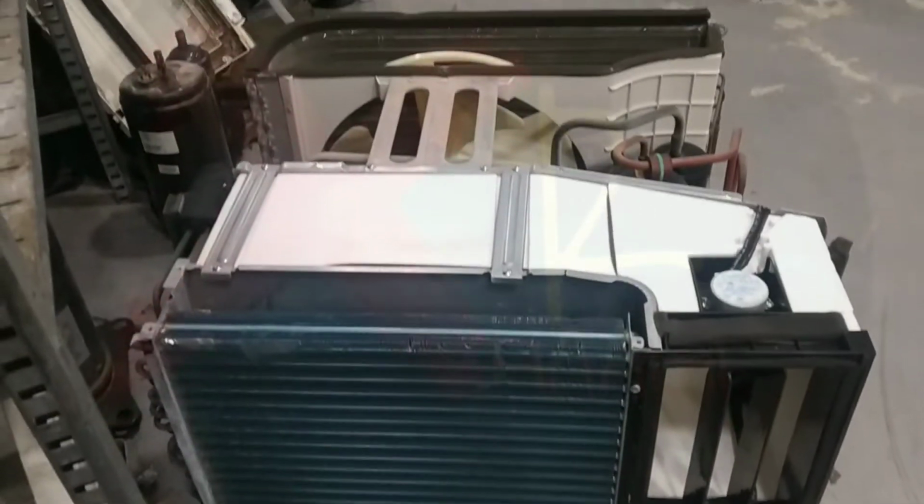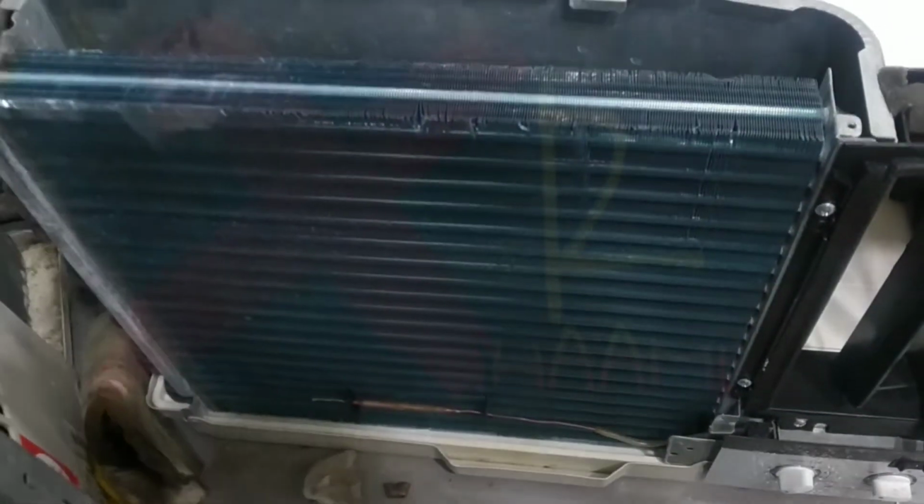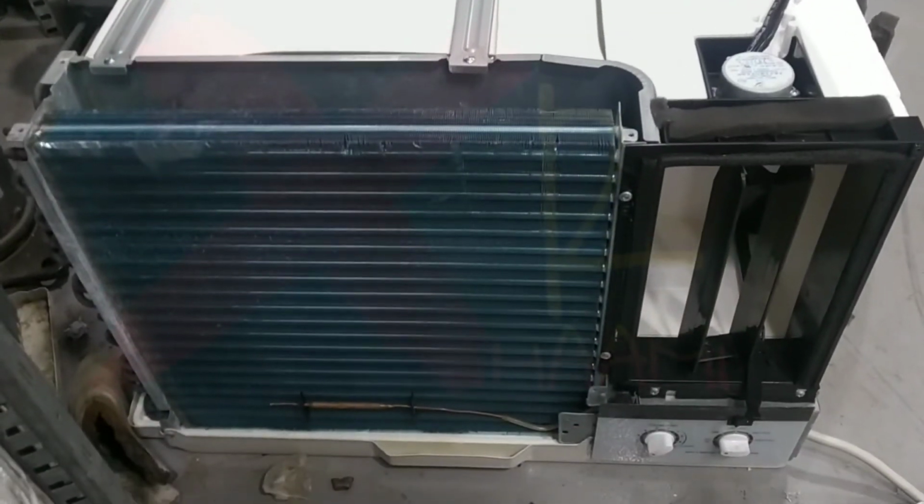This is also a reason for icing over: if your air filter, cooling coil and condenser coil are blocked with dust. As you can see, this is the condenser coil. Mostly we do not clean our air filter on time. As you can see, this is the air filter. Because of that, the cooling coil also becomes dirty or choked with dust. So make sure these three parts are always clean if you face this problem.